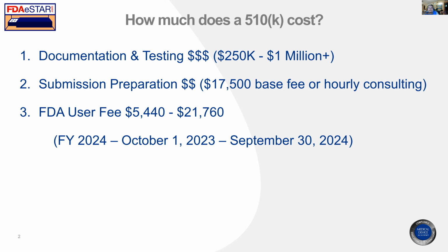So not only do you have to do in-house testing for validation of your software and document all that, which could easily be $50,000 worth of documentation alone, let alone all the testing time and development that went into it. But then in addition to that, you have to prepare cybersecurity documentation, and you're going to have to outsource penetration testing unless your company is big enough to have independent teams that haven't worked on each other's projects. So unless you have somebody completely outside of the development team for your cybersecurity penetration testing, you'll have to outsource that testing. So something to keep in mind, when you start these new projects, keep some people separate that know how to do penetration testing so you don't have to outsource that.